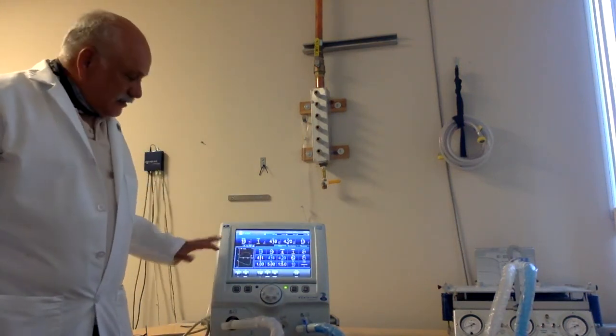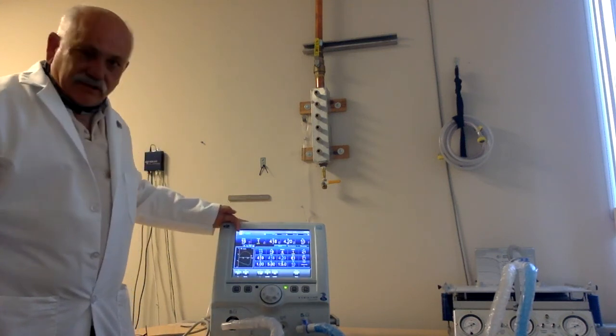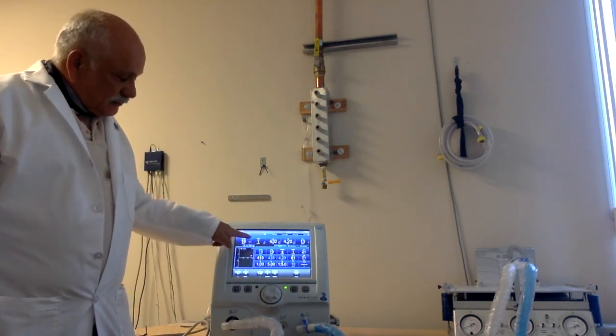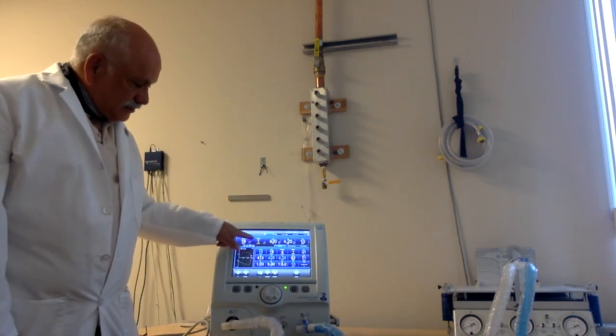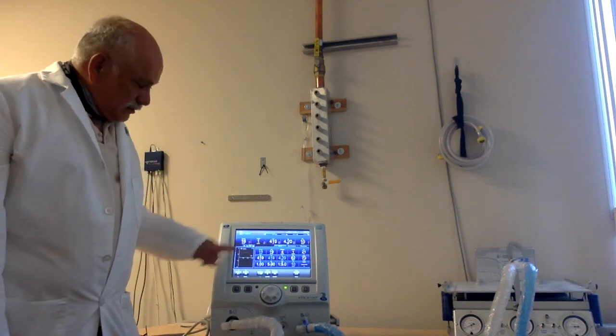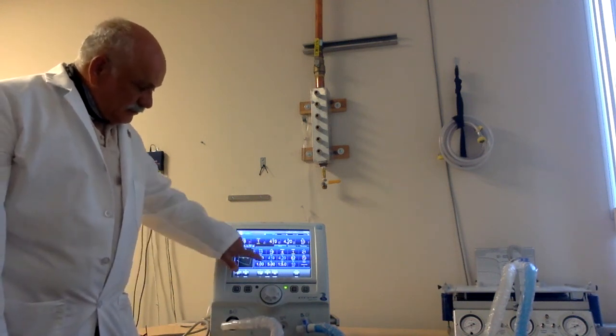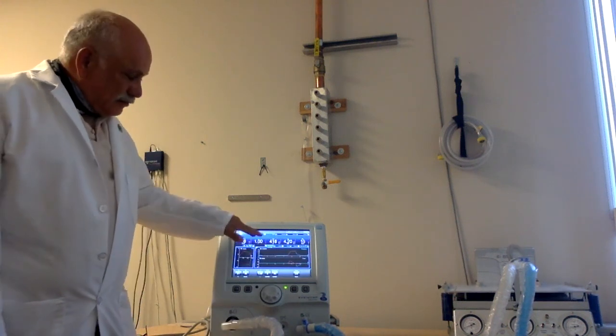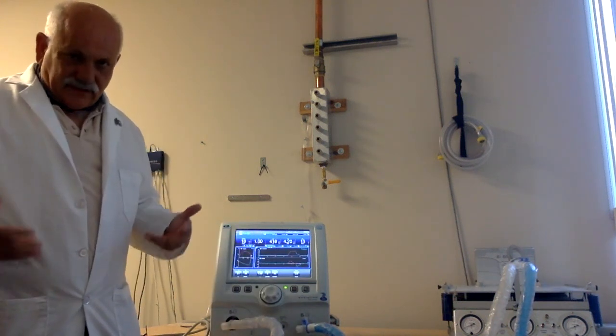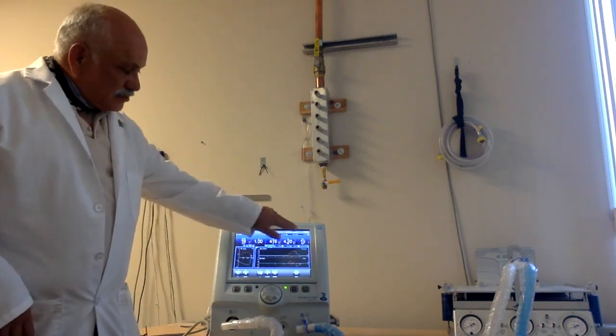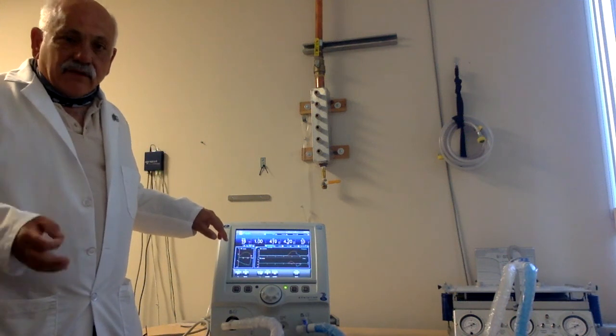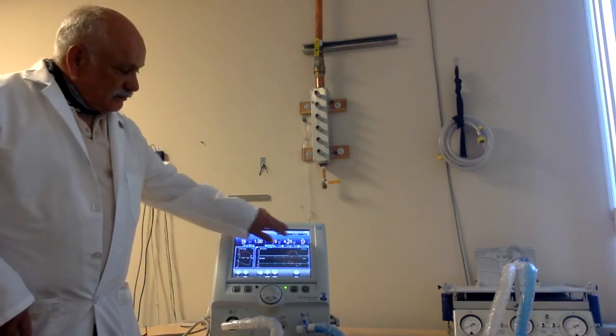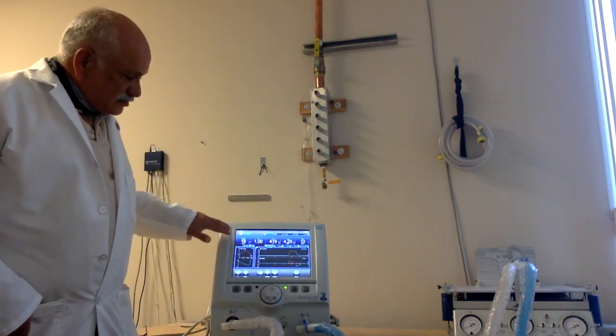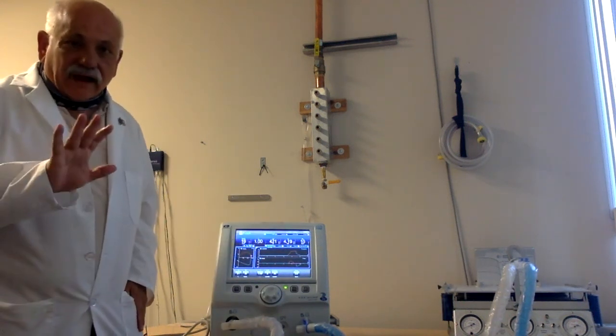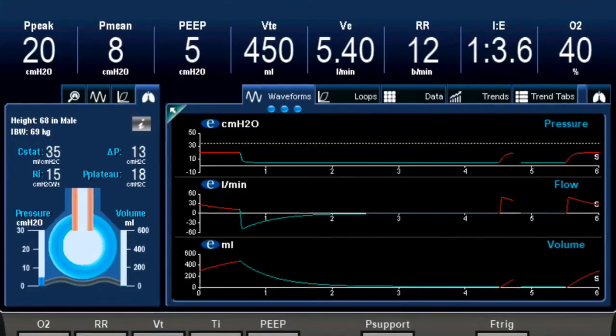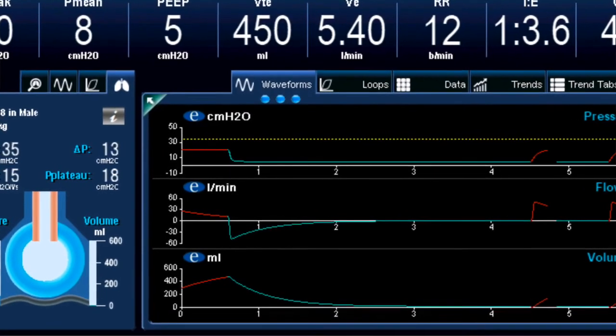Another thing that I like about this ventilator is I can choose which digital parameters I monitor. Let's say I want the tidal volume inspired, or let's say the time of inspiration up here. I hit PEEP, it turns yellow. I touch the parameter I desire, and it now replaces that. Now, of course, all the parameters are continuously monitored, but those that I deem important, generally related to the mode of ventilation or the patient condition, can be placed up above in this digital strip. Right now, I've chosen 5 parameters to monitor, but you can choose 8.